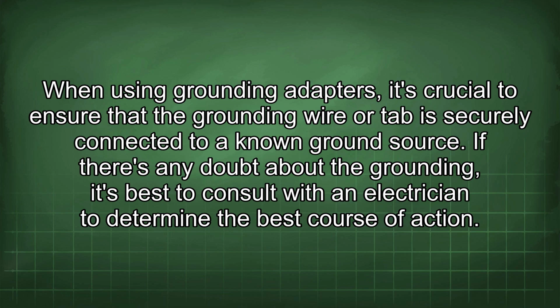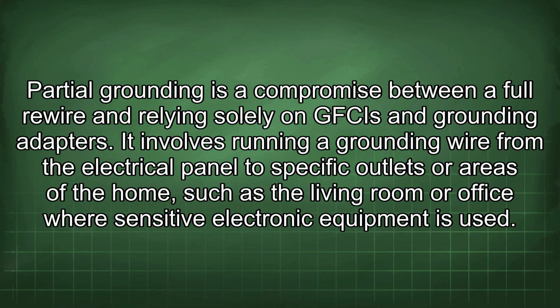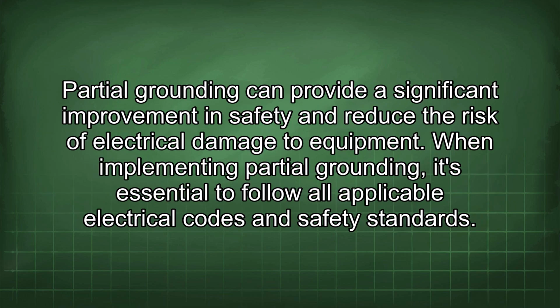When using grounding adapters, it's crucial to ensure that the grounding wire or tab is securely connected to a known ground source. If there's any doubt about the grounding, it's best to consult with an electrician to determine the best course of action. Partial grounding is a compromise between a full rewire and relying solely on GFCIs and grounding adapters. It involves running a grounding wire from the electrical panel to specific outlets or areas of the home, such as the living room or office where sensitive electronic equipment is used. Partial grounding can provide a significant improvement in safety and reduce the risk of electrical damage to equipment.